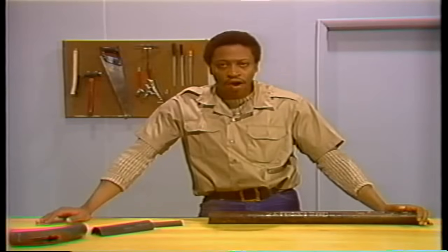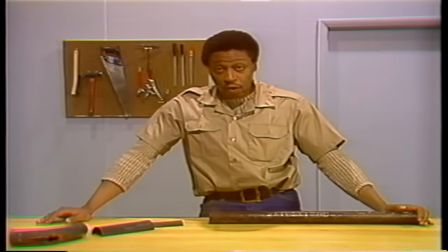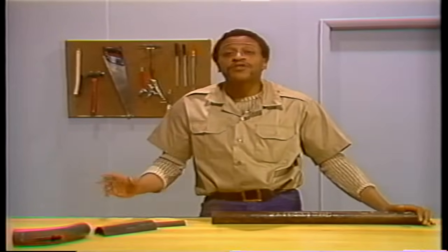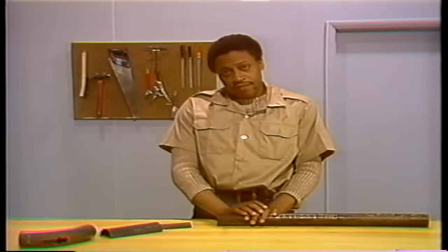Overheating is the most common cause of boiler tube failure. Overheating can result from deposits from boiler water, inadequate flow of water or steam through the tubes, improper flow of hot gases through the boiler, refractory failure, and improper operation. Boiler tubes are constantly exposed to intense heat — in fact, the temperature is so high that it could melt the tubes. The reason they don't melt is that the water and steam flowing through them keep them cool, although that water and steam are very hot, they are still cool enough to keep the tubes from melting.